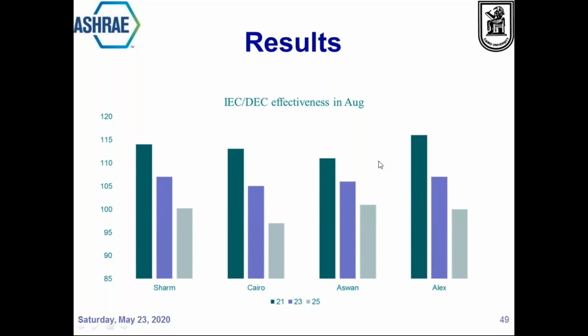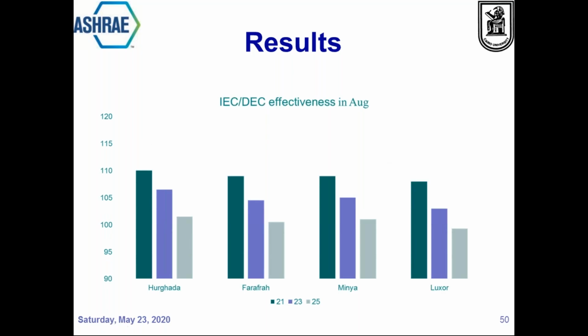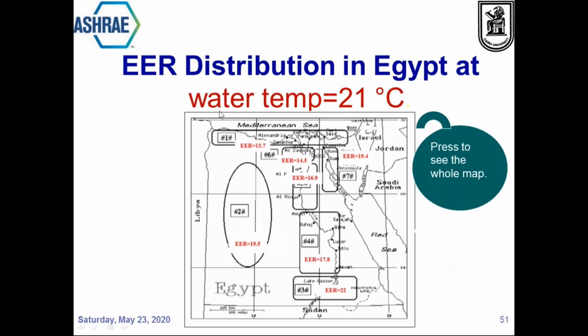You may ask me how sure the results are to be repeated. We repeated the results at different times for certain locations, and it is repeated within plus or minus 0.5%. For example, here, that's the energy efficiency ratio. So if I have an evaporative cooling system in this zone, the energy efficiency ratio will be 19.5.